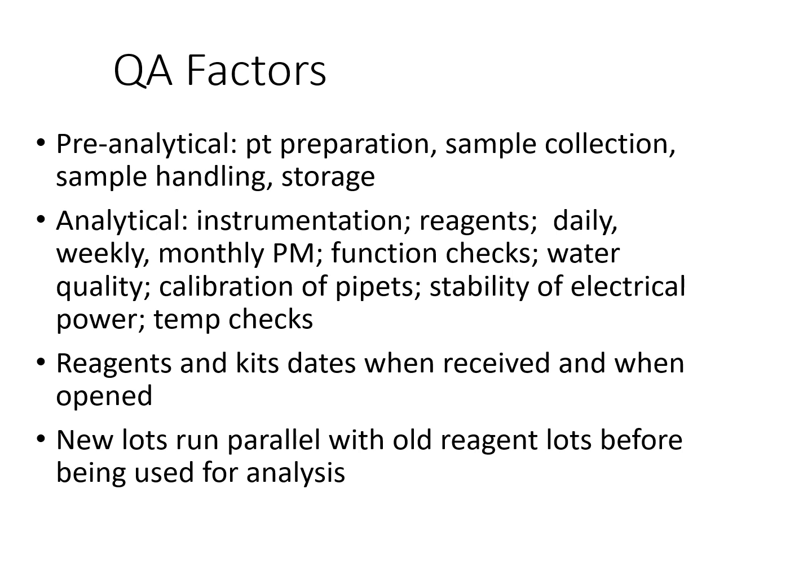On new lots, particularly standards and control material, will be run parallel with old lots before using for analysis. Again, you need to determine if your new lot is going to cause a shift in your confidence interval for your controls.